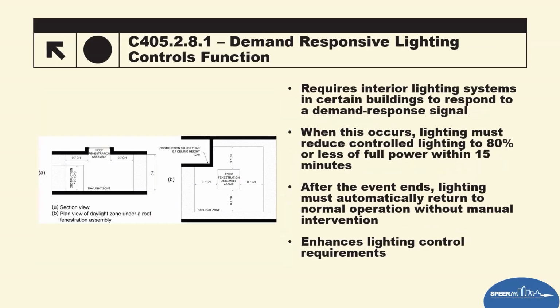And then the demand responsive lighting controls function. This still continues to be clarified or adjusted. So basically in C405.2.8.1, in buildings where this is adopted, the lighting systems must be able to receive a demand response and rapidly reduce power to less than or equal to 80% of the full output. In the 2021, I believe that was 50, now it's 80. Within 15 minutes of the signal, once the event ends, the light turns back to automatic power.